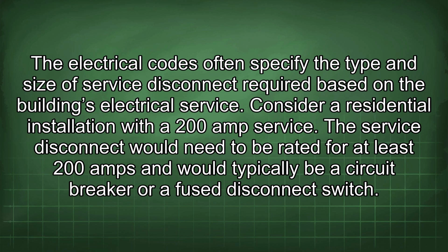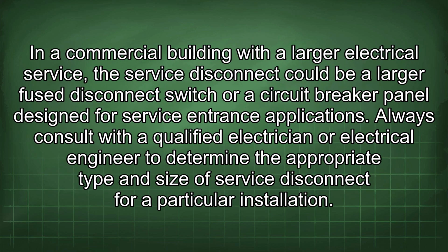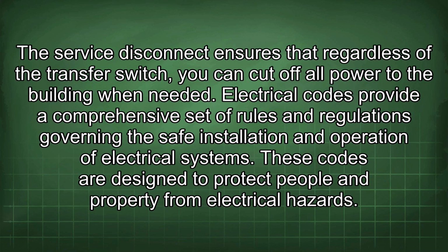The electrical codes often specify the type and size of service disconnect required based on the building's electrical service. Consider a residential installation with a 200 amp service. The service disconnect would need to be rated for at least 200 amps and would typically be a circuit breaker or a fused disconnect switch. In a commercial building with a larger electrical service, the service disconnect could be a larger fused disconnect switch or a circuit breaker panel designed for service entrance applications. Always consult with a qualified electrician or electrical engineer to determine the appropriate type and size of service disconnect for a particular installation. The service disconnect ensures that regardless of the transfer switch, you can cut off all power to the building when needed.